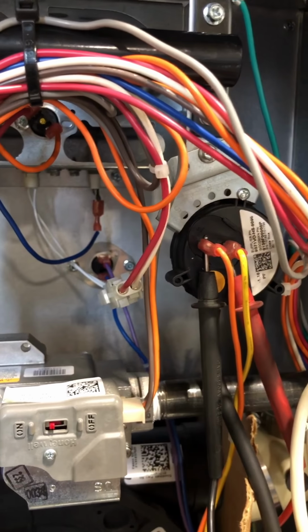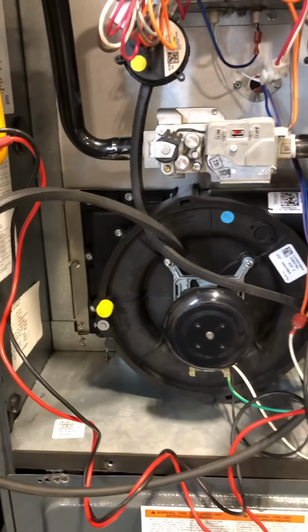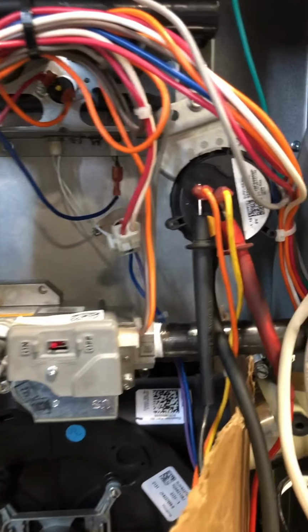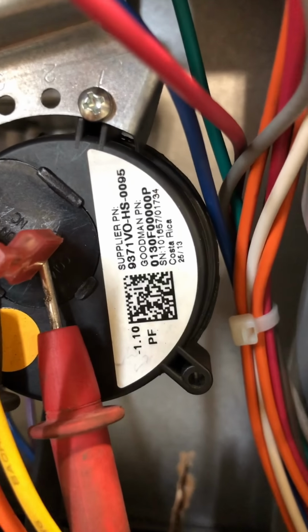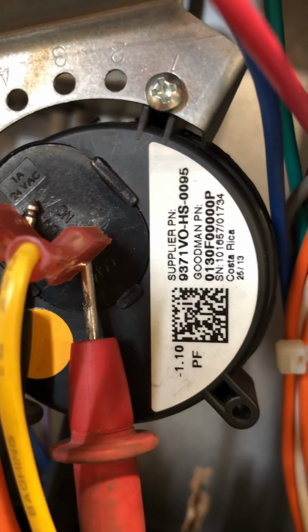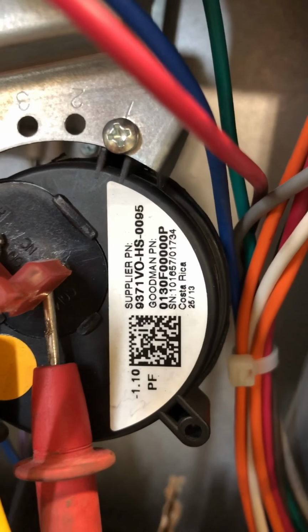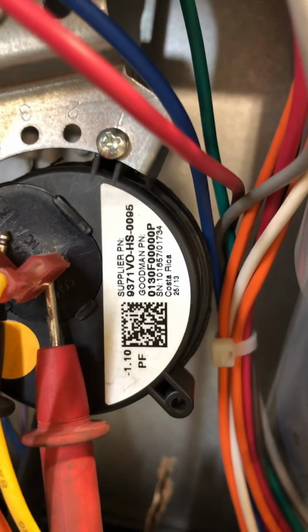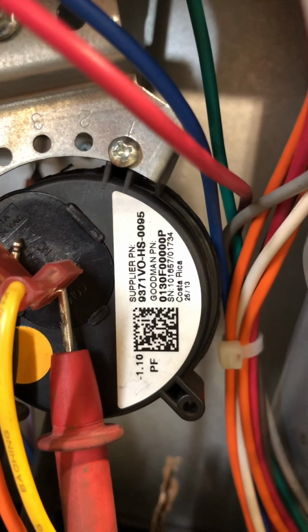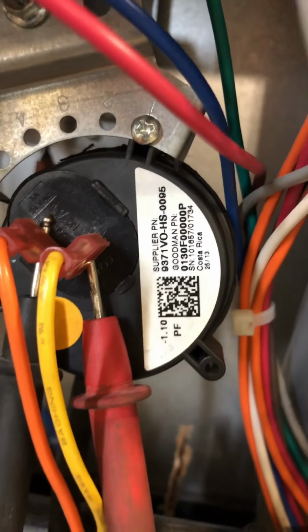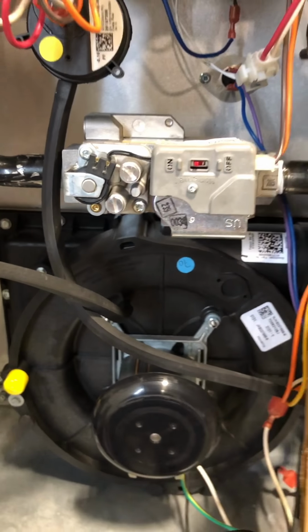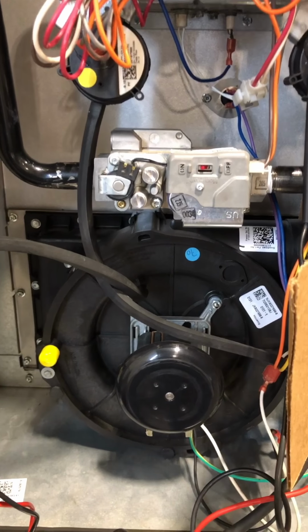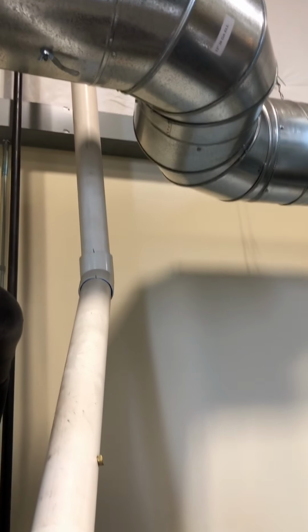As soon as that happens, then this pressure switch needs to close based on the negative pressure that we're pulling in here. And every switch is going to be a little different. We'll zoom in here a little bit on this one. This one is saying it needs a negative 1.10 inches of water column pressure on it in order for this switch to close. So that's what the manufacturer has deemed is the proper vacuum to prove that this inducer motor is pulling enough of a negative pressure inside that heat exchanger that we're going to pull all that nasty stuff that we burn up and out the flue pipe.